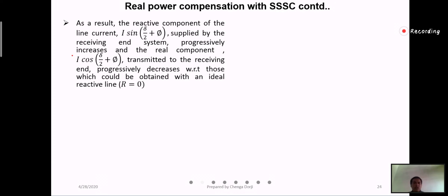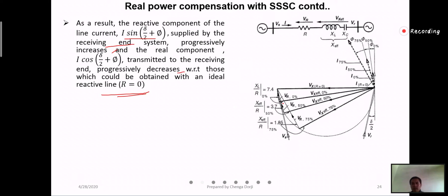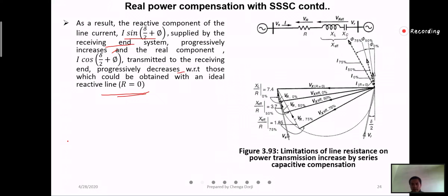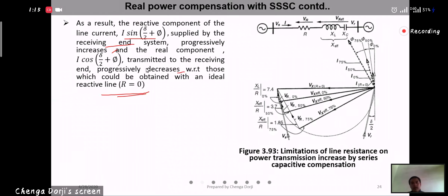As a result of increasing series compensation, the reactive component of the line current I·sin(δ/2) supplied by the receiving end system progressively increases, and the real component transmitted to the receiving end decreases. So reactive component will increase and active component will decrease. Therefore, the limitation of line resistance on power transmission increases with increasing series capacitive compensation, and the power handling capability decreases with increasing degree of series compensation.